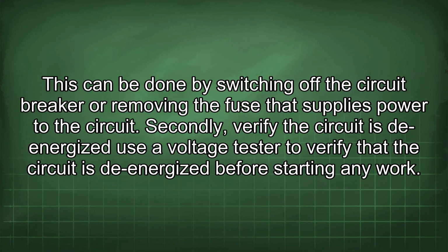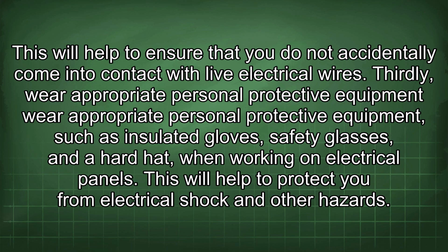This can be done by switching off the circuit breaker or removing the fuse that supplies power to the circuit. Secondly, verify the circuit is de-energized. Use a voltage tester to verify that the circuit is de-energized before starting any work. This will help to ensure that you do not accidentally come into contact with live electrical wires.